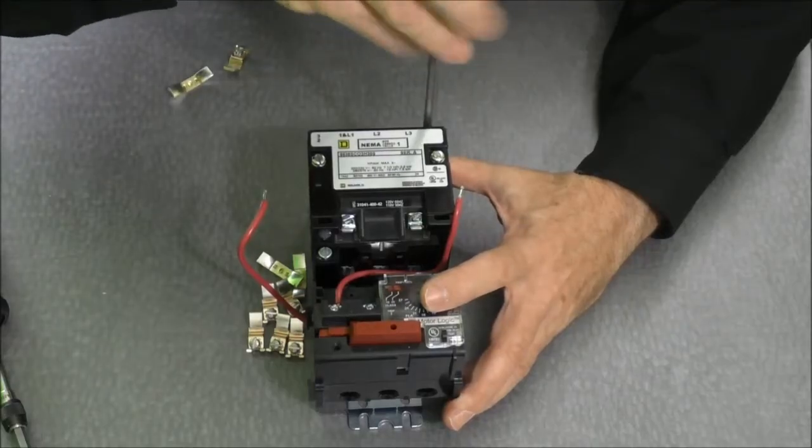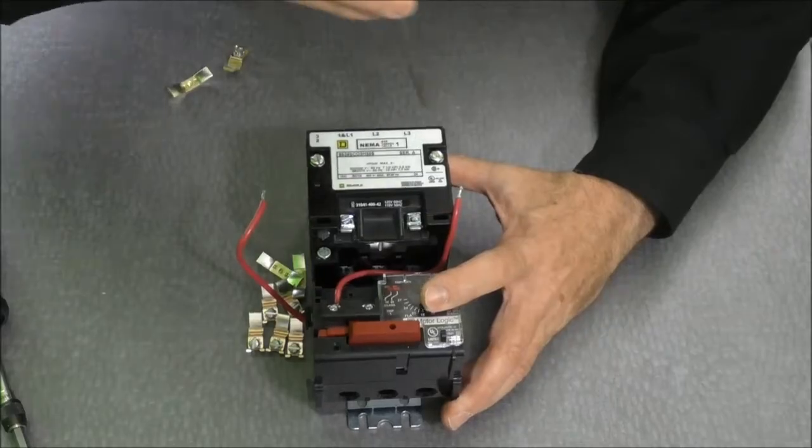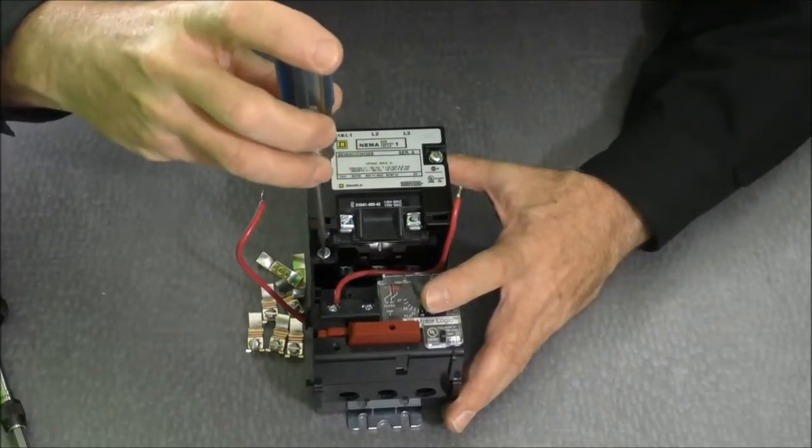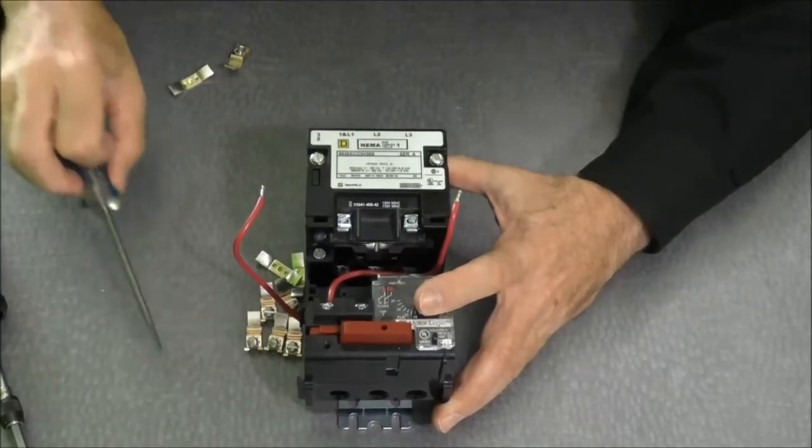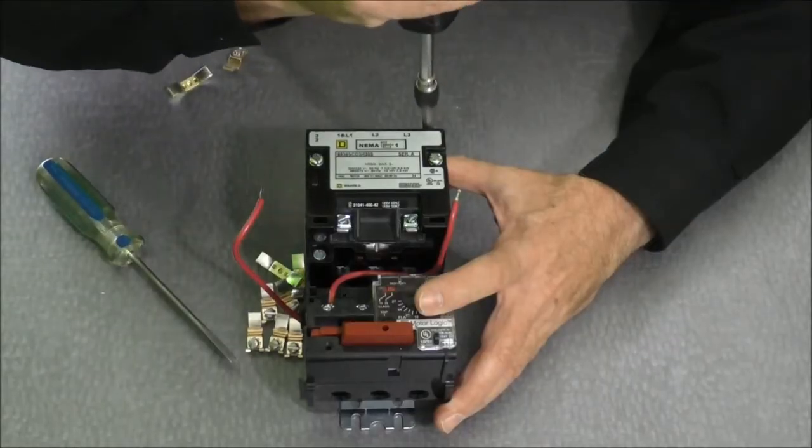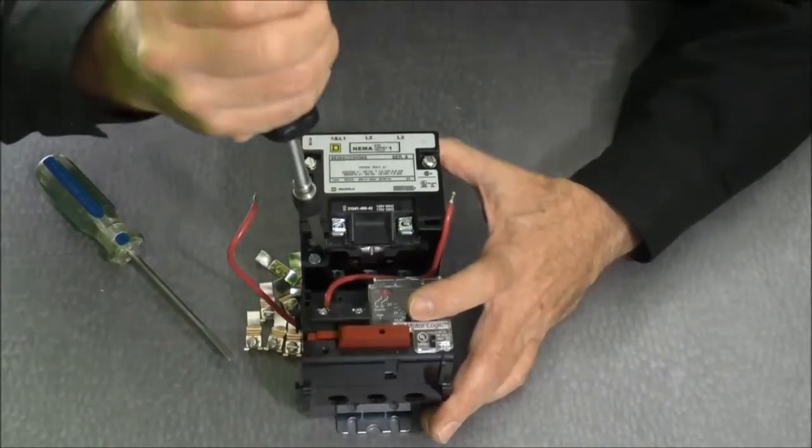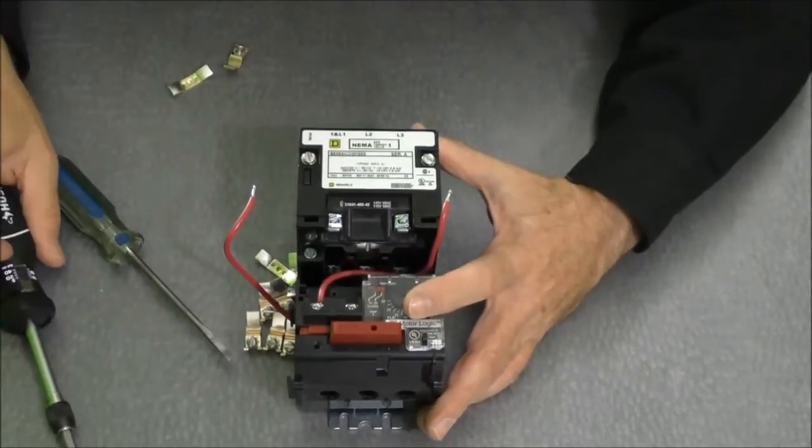I'm going to tighten the screws. These screws have an 18 to 21 inch pound rating. So I'm going to use my torque driver to torque that down. Once the torque driver begins to ratchet we know that we're tight. And we're good to go.